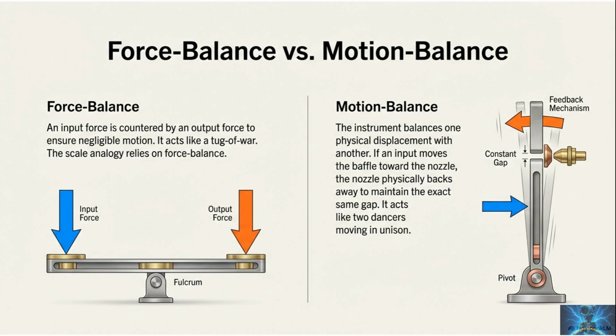Force balance versus motion balance. Force balance means an input force is countered by an output force, so there is almost no movement. It acts like tug of war, where both sides pull until the motion becomes negligible. Motion balance is different. One physical displacement is balanced by another displacement to maintain a constant gap. If the input moves the baffle toward the nozzle, the nozzle backs away so the clearance stays the same. Both are feedback systems, but they balance different things.